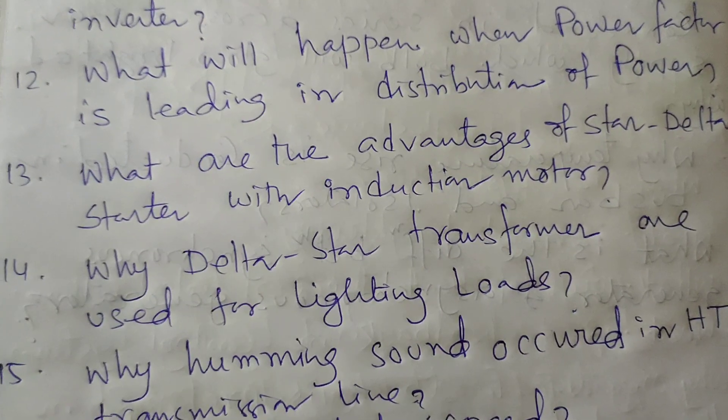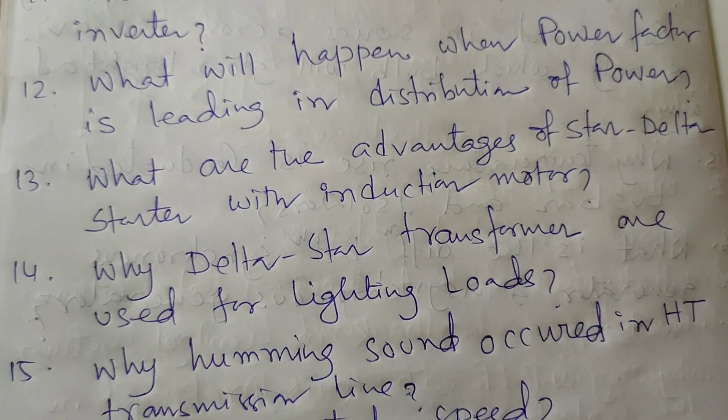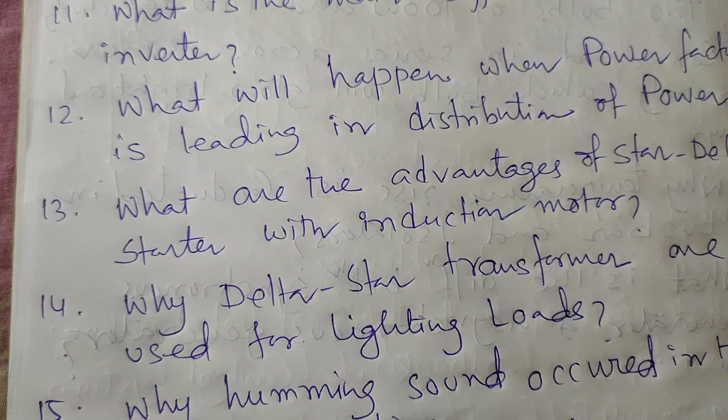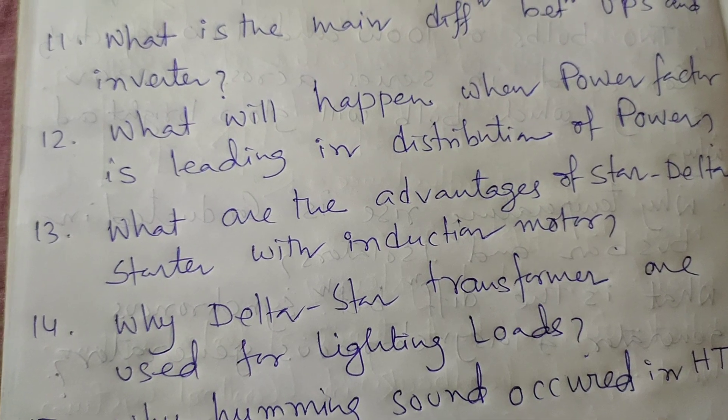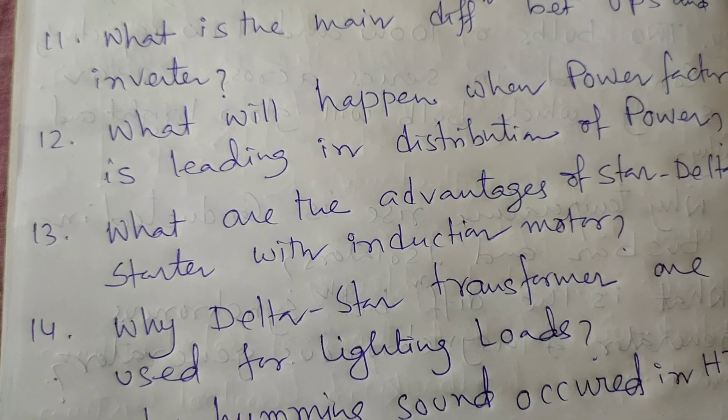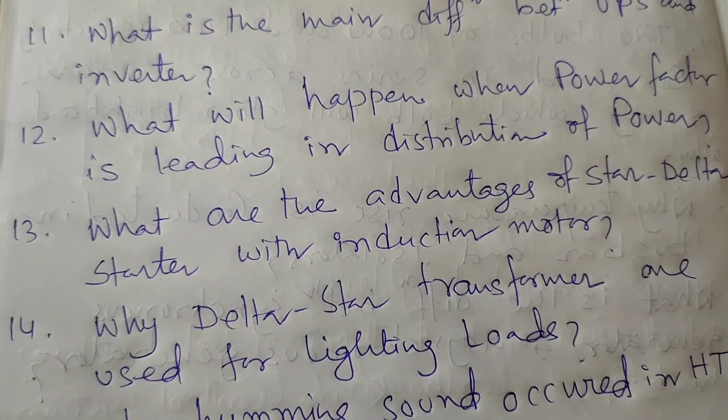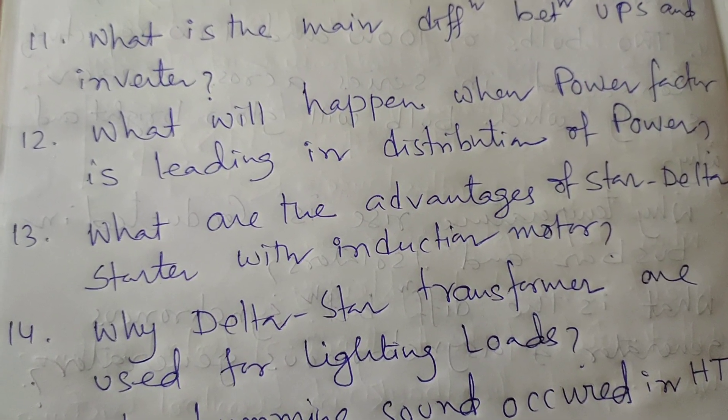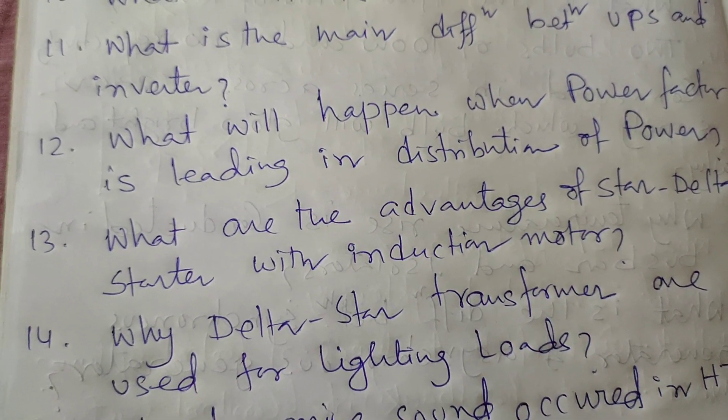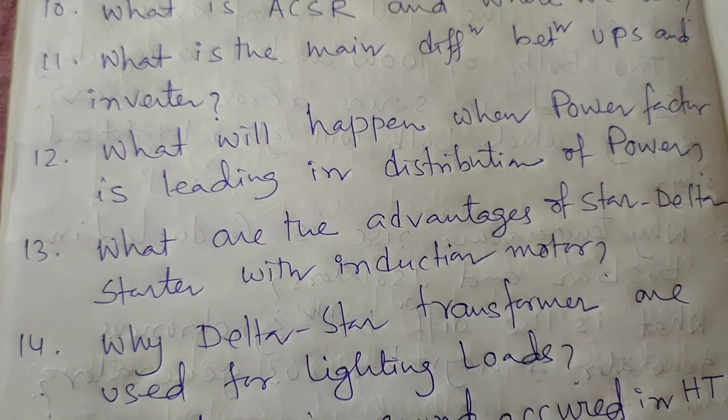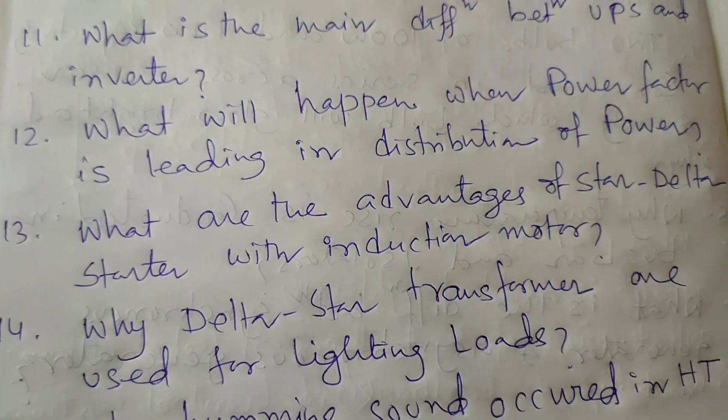Next question: Why are delta-star transformers used for lighting load? For lighting load, neutral conductor is a must, so the secondary must be star winding. This lighting load is always unbalanced in all three phases. To minimize current unbalance in primary, we use delta winding in the primary. So delta-star transformers are used for lighting load.